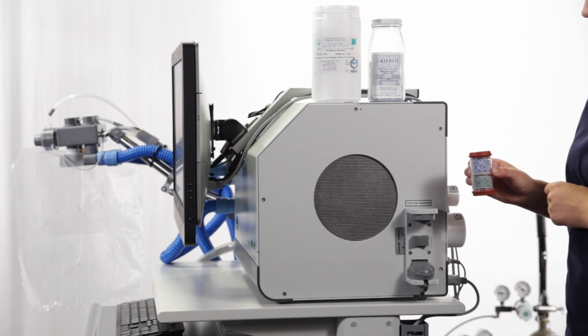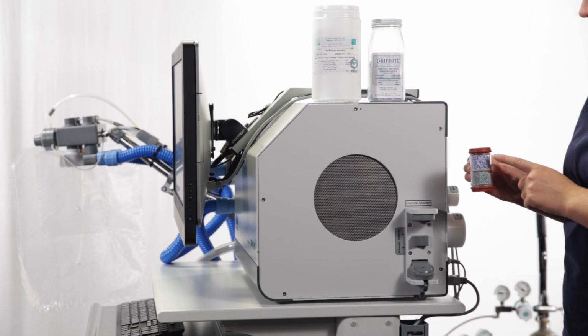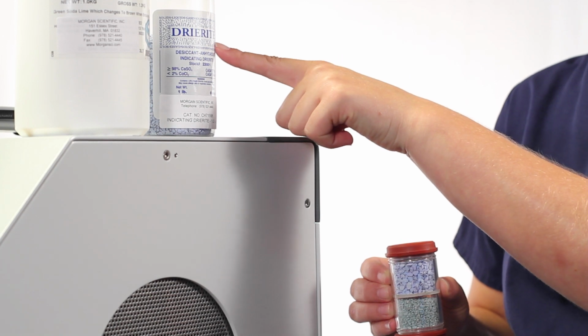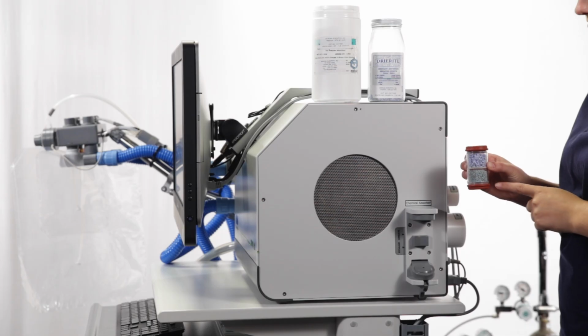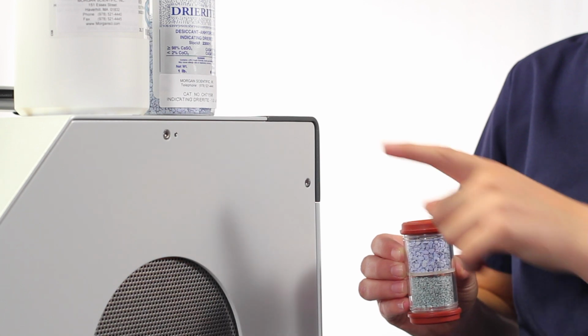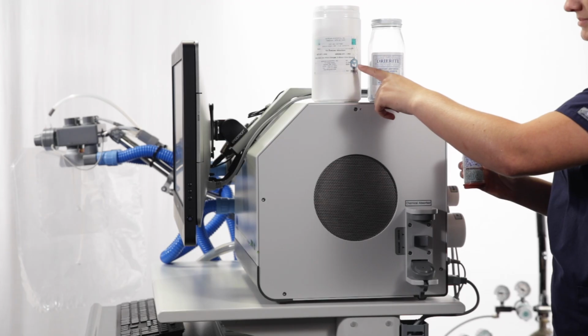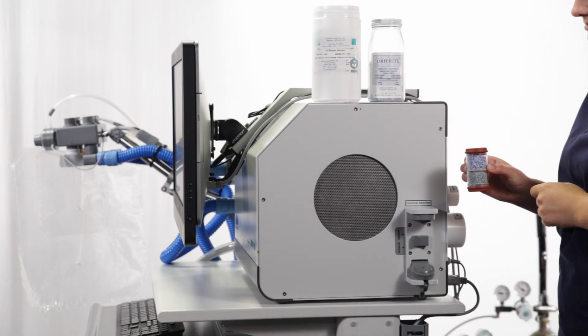There are two chemicals used in the absorber column. The blue crystals are Drierite, which absorbs water vapor. This will likely need changing every day. The green granules are soda lime, which absorbs carbon dioxide. This chemical will likely only need changing twice per week.